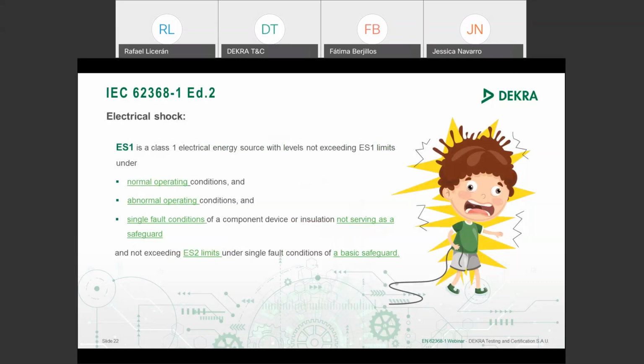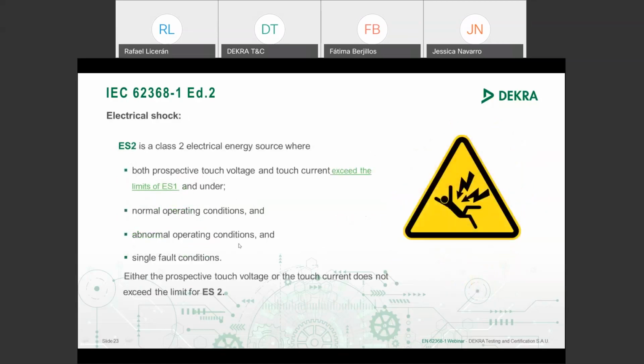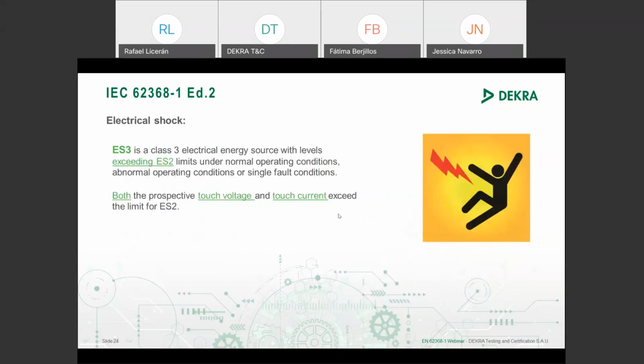In this way, I use ES1 as an electricity level of energy that does not cause injury for people, taking into account that we have to check this electricity port in normal condition, abnormal condition, and single fault condition. Level ES2 means that this equipment has a different electrical part that cannot be accessible for everybody. And ES3 is like the old standards say, the hazardous voltage.